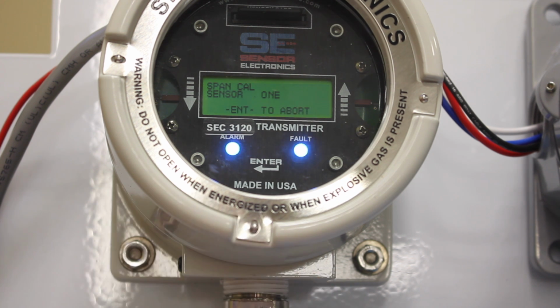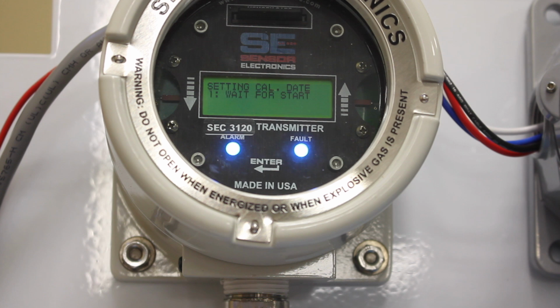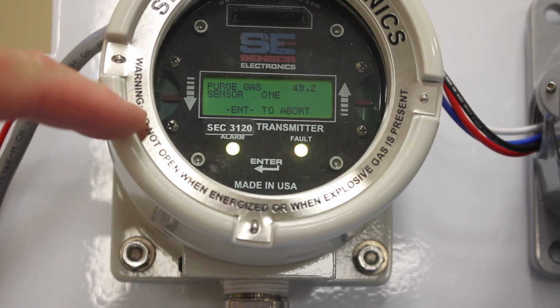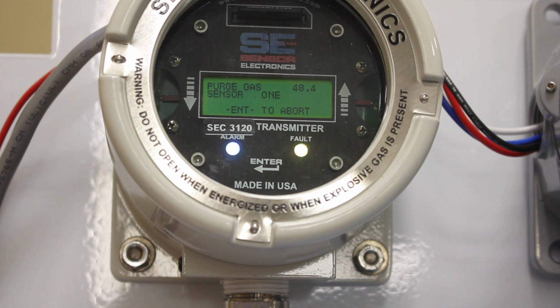So we'll select enter to span it, and now it goes through its spanning procedure, and once it's completed, it will just stay in the calibration mode, so it doesn't turn any alarms on or anything like that, because right now it's done, and it's reading 49.2. So I turn the gas off, and now we let the gas dissipate out of the sensor, or we could blow clean air into the sensor in order to purge the sensor of that gas. So that's what I'll do now, is I'll just apply clean air to the sensor.